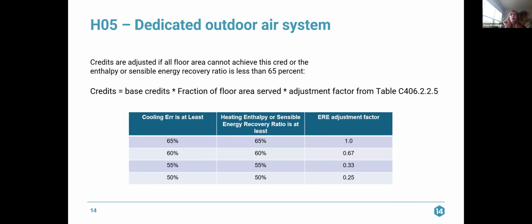And then if your cooling or heating enthalpy or sensible energy recovery ratio doesn't meet that 65%, you're also going to have this ERE adjustment factor. We'll go through an example here, but you'll see that if your cooling energy recovery ratio is at least 60% and your heating enthalpy recovery ratio is at least 60%, then your ERE adjustment factor is 0.67, and it goes down from there. That 65% is the base requirement of H05, so your adjustment factor is 1.0. If you have an ERV with greater than 65% heat recovery ratio effectiveness, you do not get additional credits.